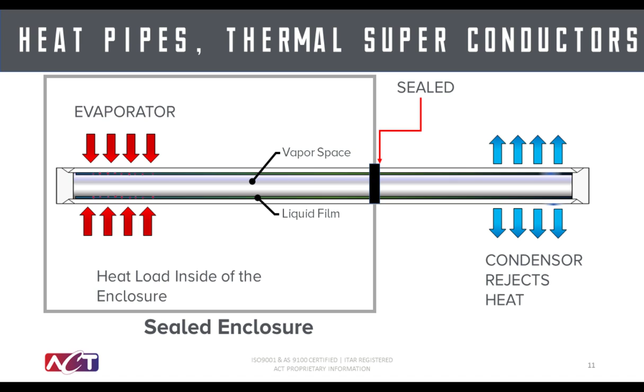In this capability, we are taking advantage of the latent heat of vaporization of that working fluid in the evaporator area. We are then transporting heat effectively to the condenser region, where the working fluid is condensed back into the wick and then returning to the evaporator area via capillary action to create a heat transfer cycle. Again, we'll talk about how this is incorporated into the next type of enclosure cooling thermal solution, but here we are able to promote the seal, effectively encapsulating heat transfer between certain sealed areas.